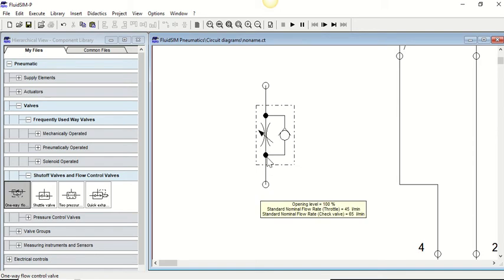Because what happens is if air is coming in this way, it can't go up this pathway here because the ball and the seat here is blocking it. It has to go through the reduction here, the needle pin. So if we're reducing, the airflow coming out gets reduced. On the way back, if air is flowing back down this way, it actually can go down here, and as it's blowing down this way, the ball will move out and it can blow down this way, and this is the path of least resistance, so it'll choose this way rather than going through this pathway. So only when air is flowing upstream is the air going to be reduced or increased. This is why it's called a one-way flow valve, and the arrow here, the way it's pointing up, gives you an indication of how it's working as well.